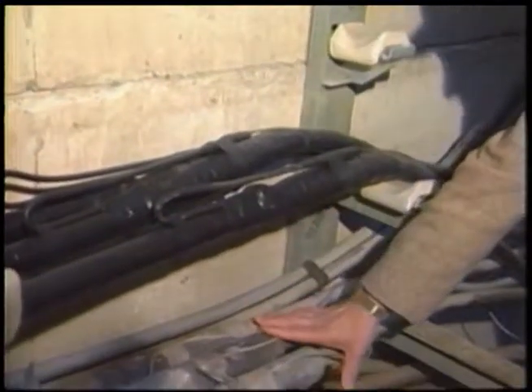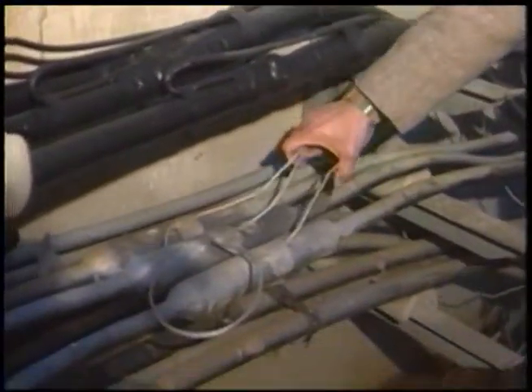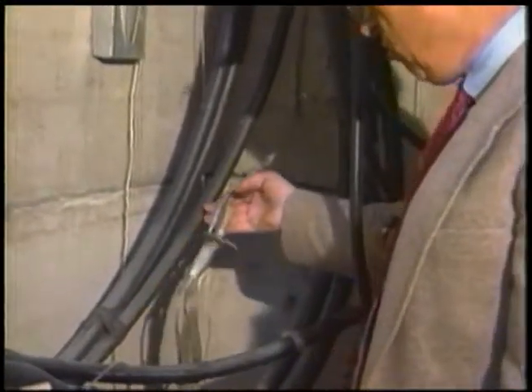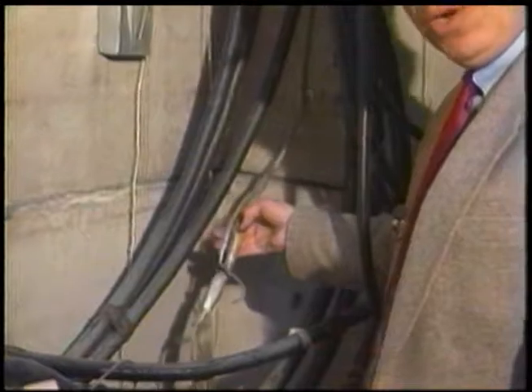Down below we have some lead cable. They also have grounds coming out. All of these grounds are attached to a common ground bond frame that runs in the manhole. It runs around the manhole, joining all the grounds together. Depending on the manhole you're in, there are different types of high voltage equipment, such as a high voltage transformer or a high voltage switch.